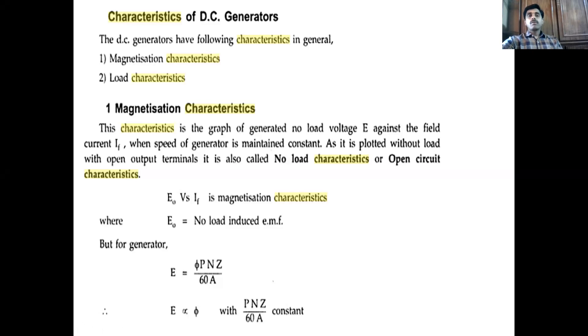Today we are going to discuss the characteristics of DC generators, which is the last topic in the third unit. There are two types of characteristics: magnetization characteristics and load characteristics. Magnetization characteristics are a graph drawn between the no-load voltage E0 and the field current If, when the speed of the generator is maintained constant. It is also called no-load characteristics or open circuit characteristics, because these plots are taken at no-load condition.